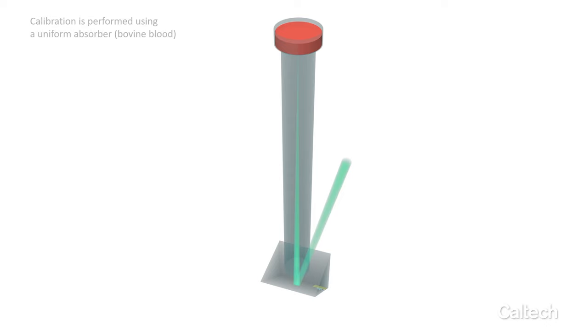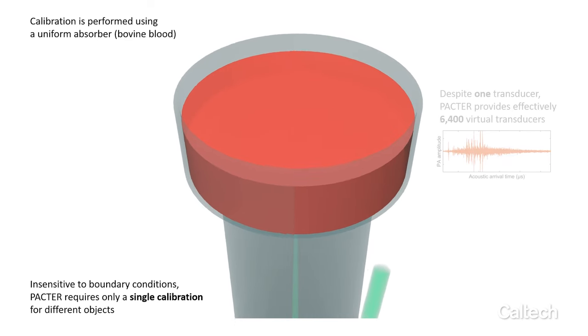The calibration is performed using a uniform absorber, such as blood. Owing to its insensitivity to the boundary conditions of the object, PACTER requires only a single calibration for different objects.